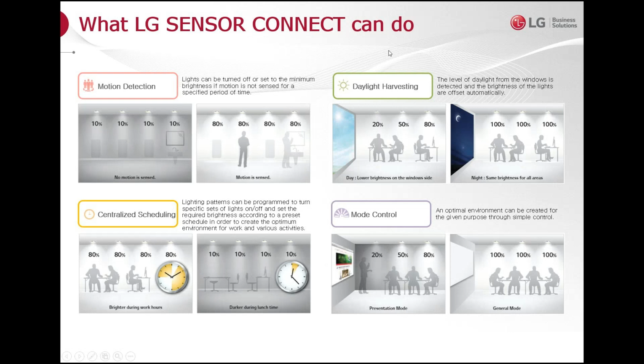and you want a certain room to be on already, you can schedule that switch to turn the lights on at 7 a.m. If you want to dim all the lights across the floor or in specific rooms, you set those switches up to dim the lights down to 50% in the evening. And then you can have an off schedule at midnight where all the lights get shut off, just in case anybody may have forgotten to turn the lights off and they don't have motion. Or there are air handling units that sometimes trip the motion and you get false ons. So scheduling can do an on or an off, and it can also modify the dim level.